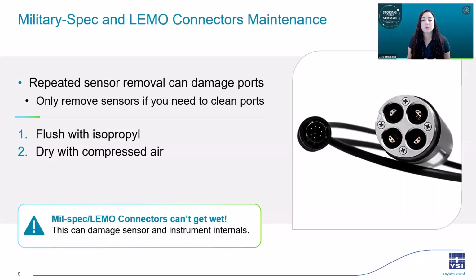And if you have an instrument with removable sensors, just so you know, we call the part where the sensors install into the instrument the bulkhead. And for an instrument that has military spec or mil-spec connectors on the bulkhead and what we call LEMO connectors on the cables, like any of the Pro Series or the Pro DSS, these connectors are not meant to get wet. And you also don't want to be removing sensors if you don't need to, because with these connectors, the repeated uninstalling and reinstalling of sensors can cause wear and tear over time.